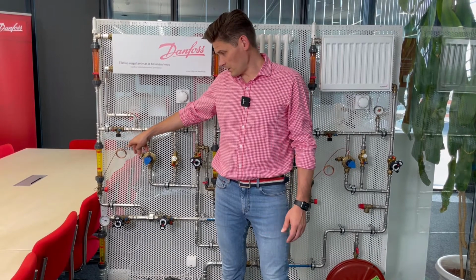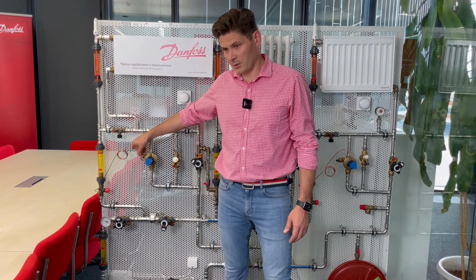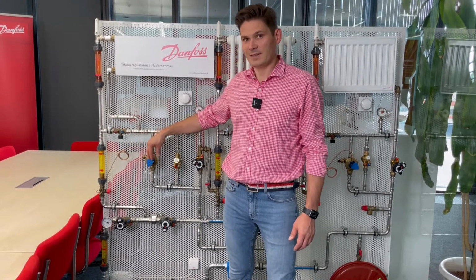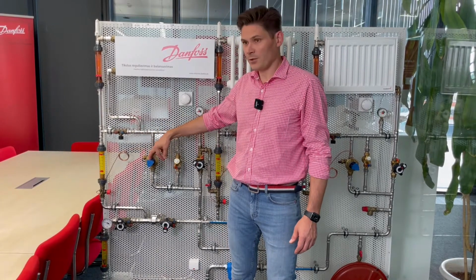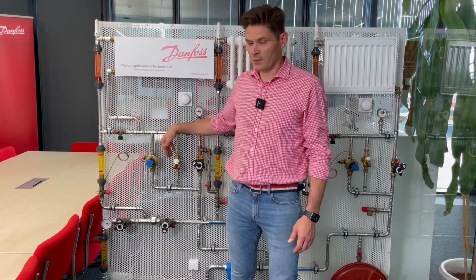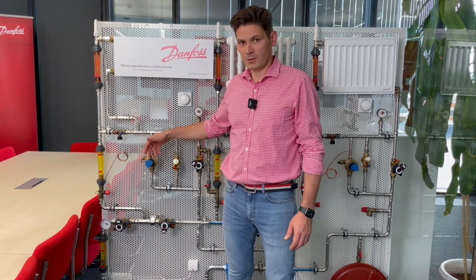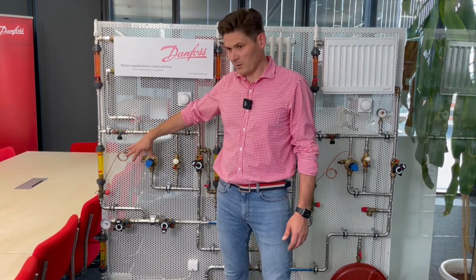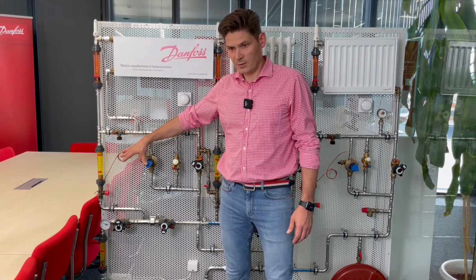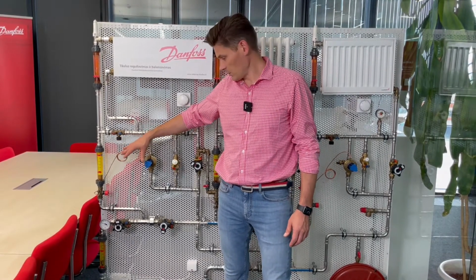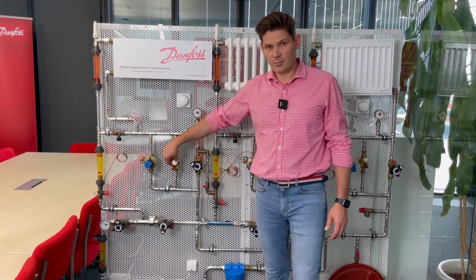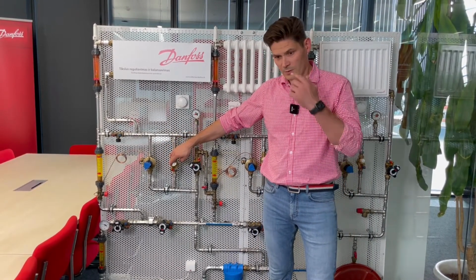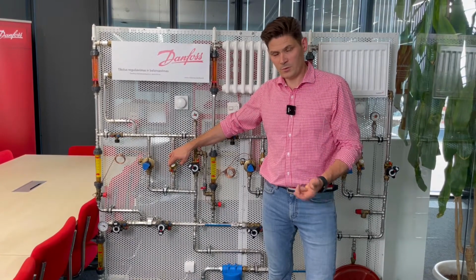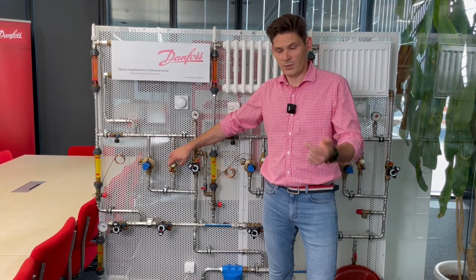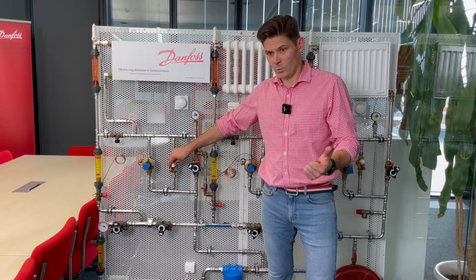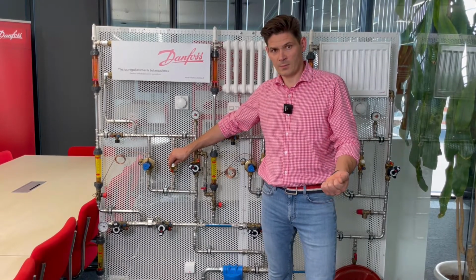There is a book, or a manual, about many different systems, and there you can check which valve is better for which application. So these ones are mainly used for radiators and for floor heating systems. The pressure independent ABQM is mostly used with fan coils, chilled beams, air handling units, air curtains, and one pipe heating system renovation.